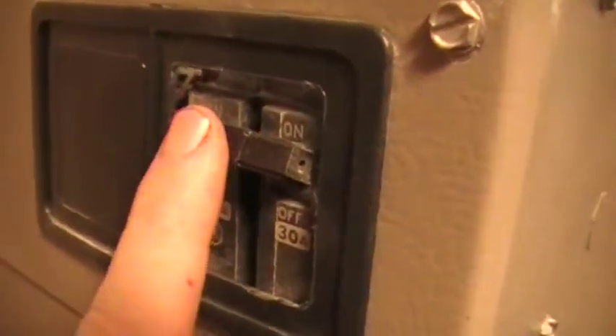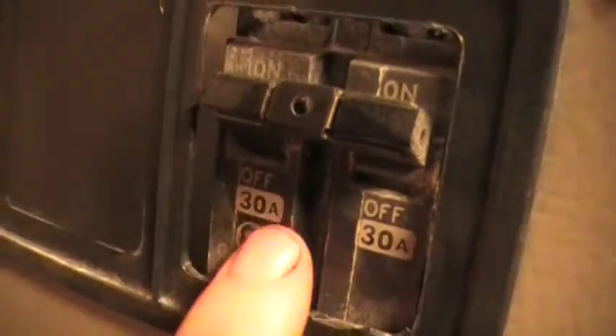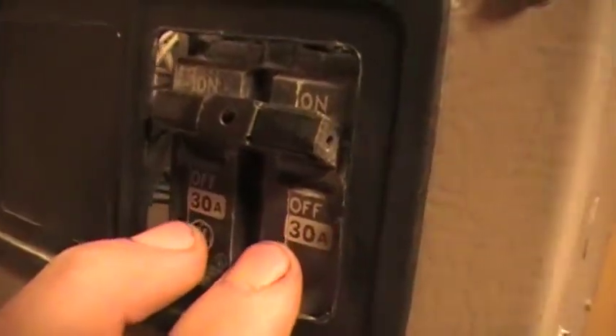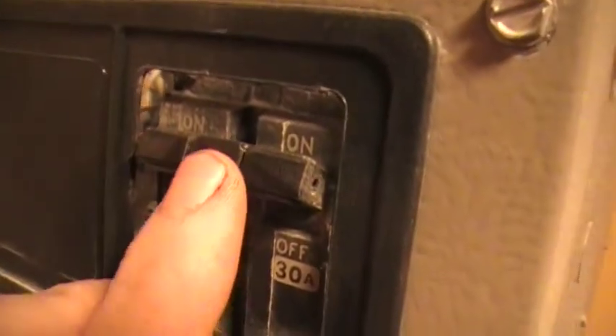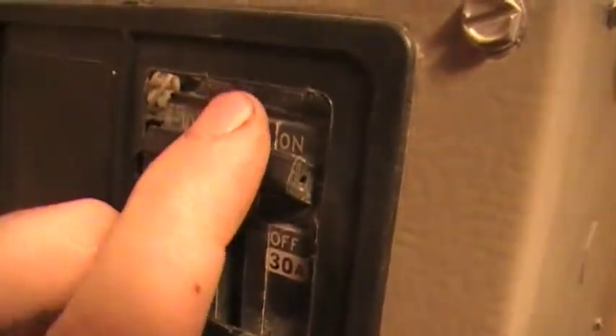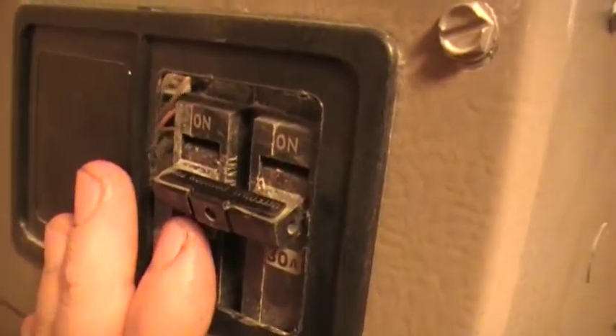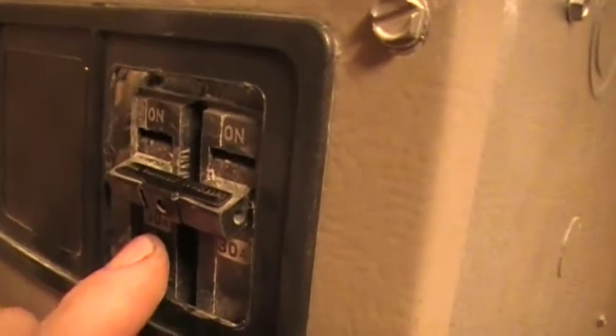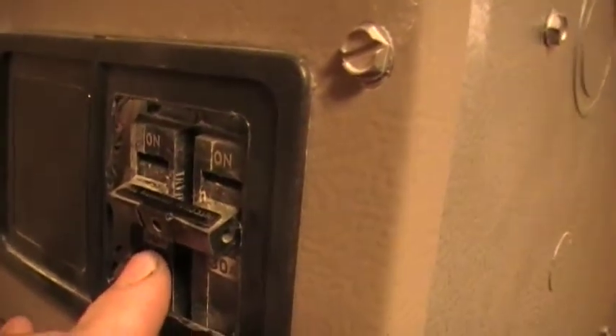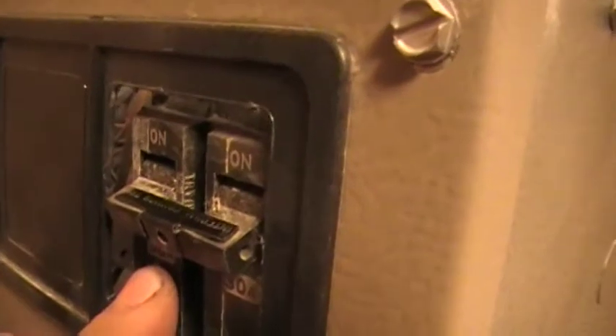It's going to have a breaker right here. This is a 30 amp, 240 volt, double pole, single throw breaker. And I'm going to cut it off. What that does is it cuts off all your control power for your unit, and neither unit will run now, indoor or outdoor. And I've taken the top off right here. I'm going to go over some of these components with you.